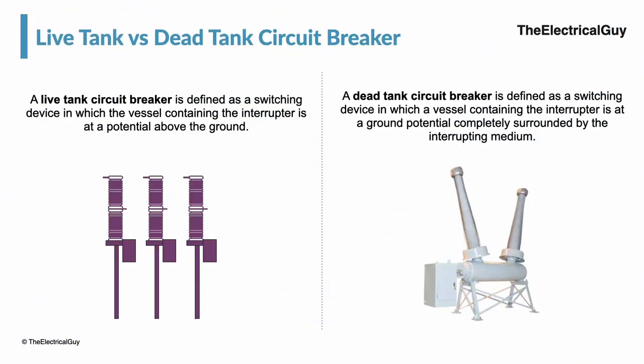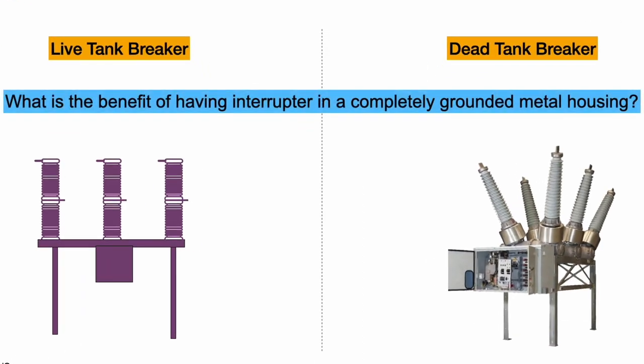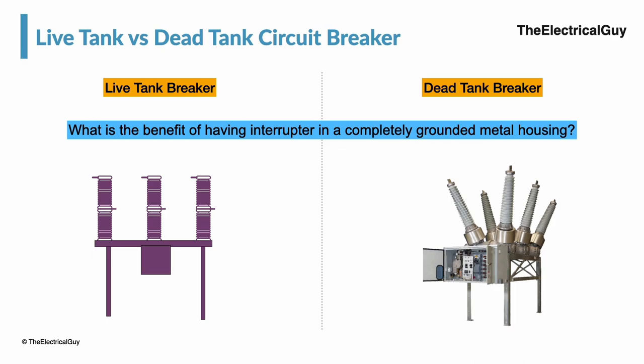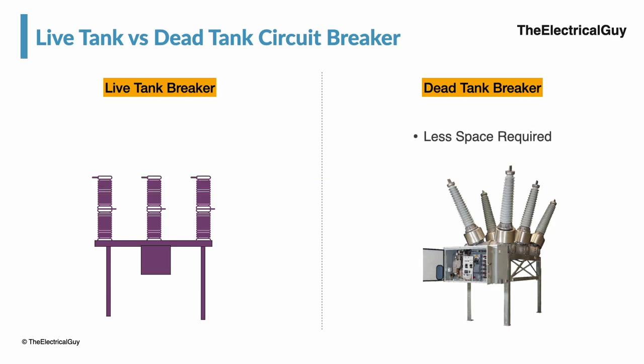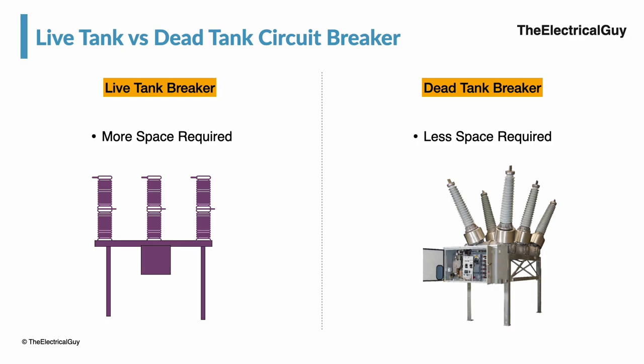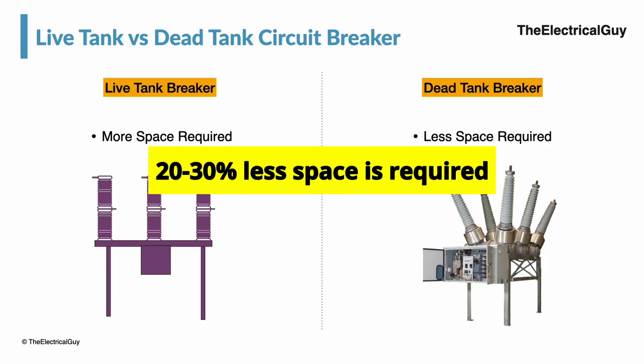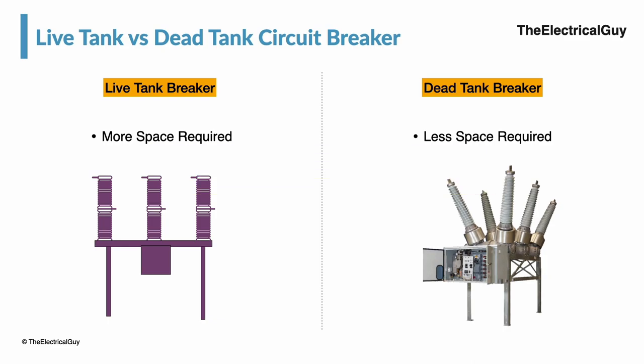We have seen one of the major differences between live tank and dead tank circuit breakers. Having the interrupter at dead or ground potential offers certain advantages. Since the complete part containing the interrupter is insulated by a dielectric medium like SF6 gas, the space required for a dead tank circuit breaker is less compared to the live tank design — approximately 20–30% less space, as you can see comparing the 145 kV dead tank and 145 kV live tank circuit breakers shown on screen.